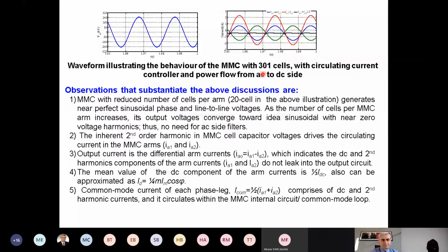And also the inherent second order harmonics in the MMC cell capacitor drives the circulating current, as we saw there. And also the output current is the differential mode current, which we explained just in the previous one. I will not go into it here. And here, this is the relationship between the output current and the DC components of the arm current, simply equal to one third of the DC. So the DC current is split into three arms. Or you can link it to the output current by this expression. And the common mode current comprises two components, which are DC and second order harmonics, as explained, and it circulates only within the MMC in the common loop, as explained earlier.